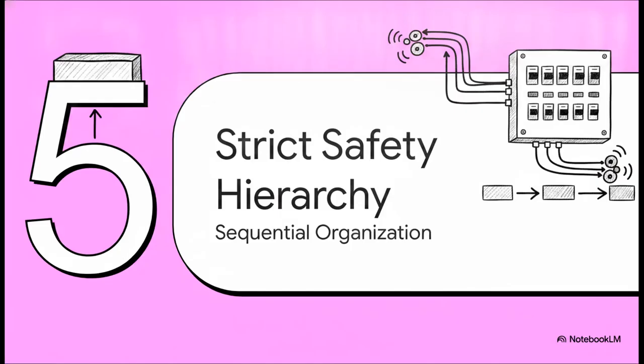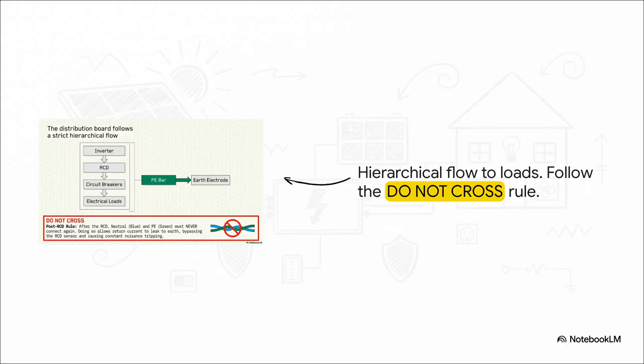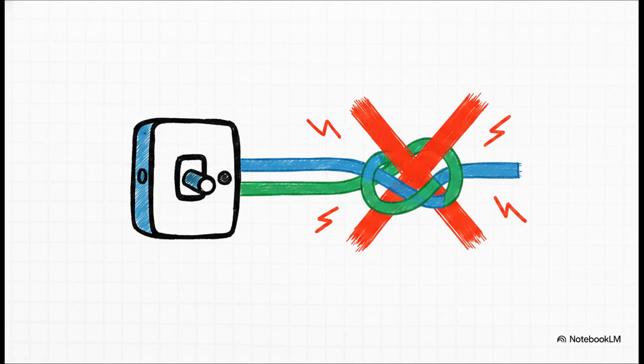Let's jump to section 5, the strict safety hierarchy. With the foundational grounding and bonding complete, it's time to organize the distribution board. Think of it like a hierarchy. Power flows down from the inverter, goes through the residual current device, or RCD, then down to the circuit breakers, and finally out to your electrical loads. And during this entire flow, that PE bar branches off to the earth electrode entirely independently, creating a very distinct safe separation. Now, this brings us to the post-RCD rule, and I really cannot overstate how important this is.